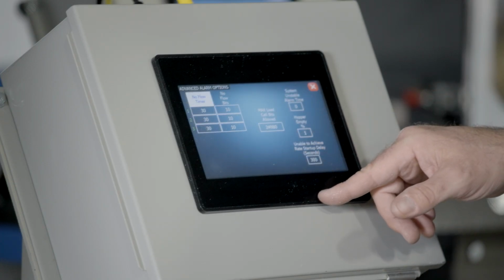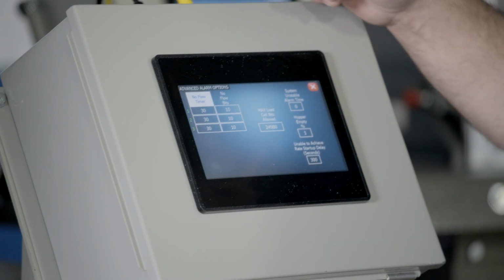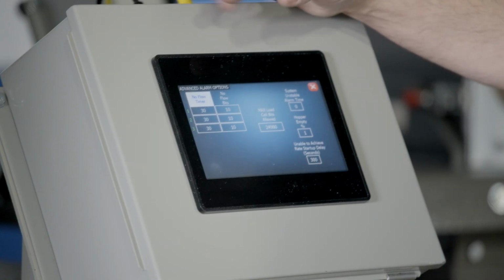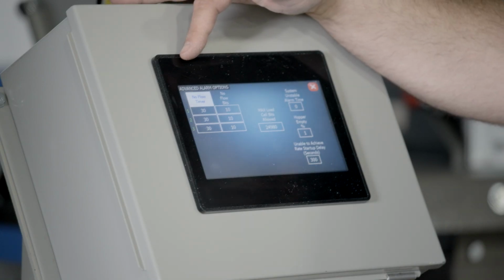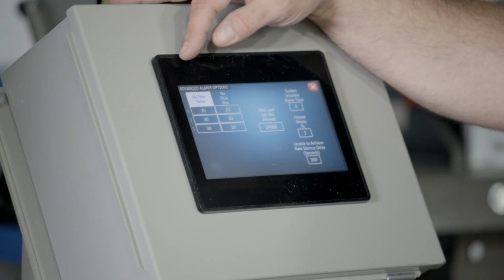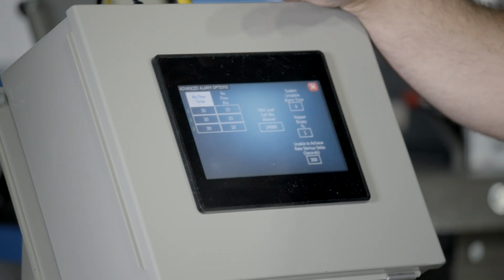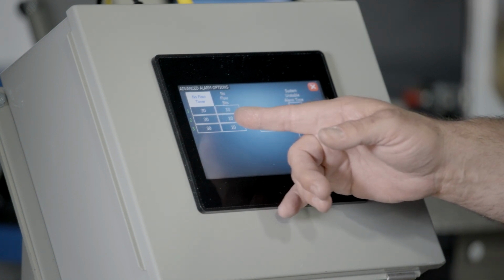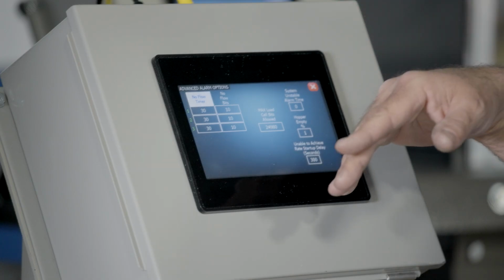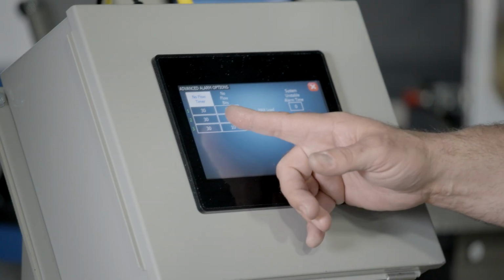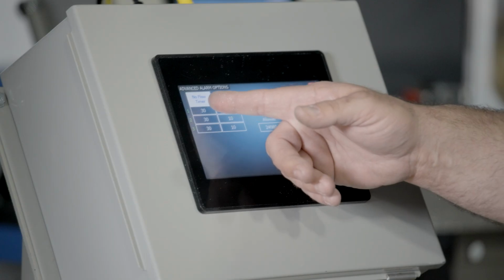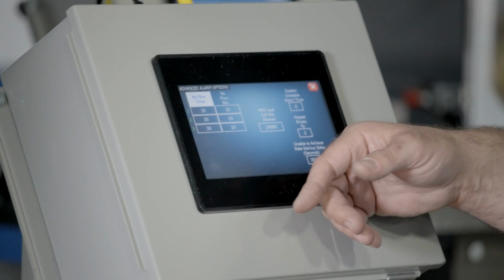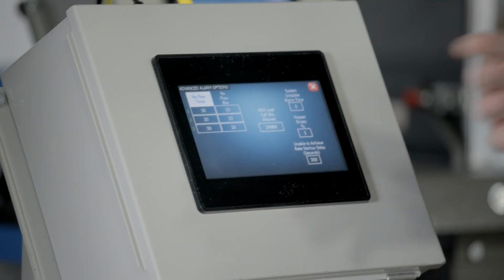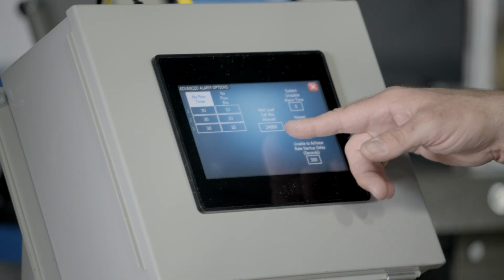Advanced alarm options. So we discussed the no flow alarm earlier. You can configure this alarm. So if you're running a very small additive and it's not losing weight very quickly, you can set a timer for your no flow. Normally it's set to 30 seconds and we want to see 10 bits move. If you don't see 10 bits move in 30 seconds, you can increase this timer to 60 seconds for 10 bits, or you can lower the number of bits we want to see. So that way you're not going to get an erroneous alarm all the time.